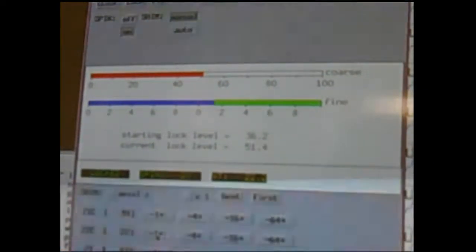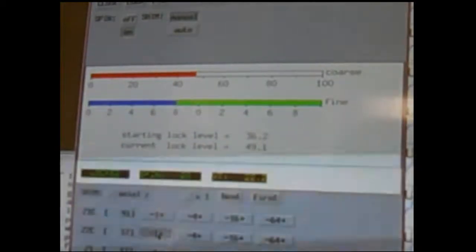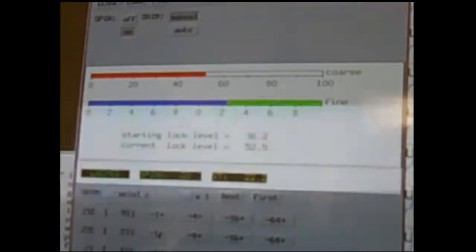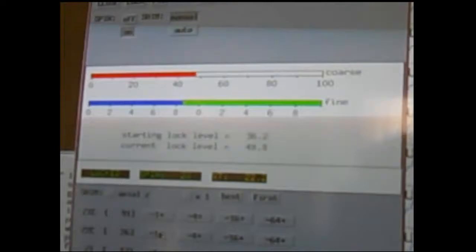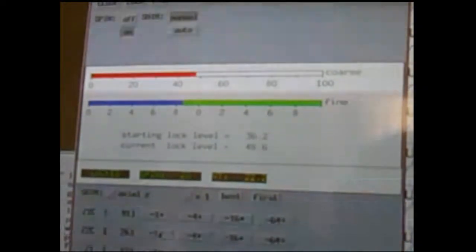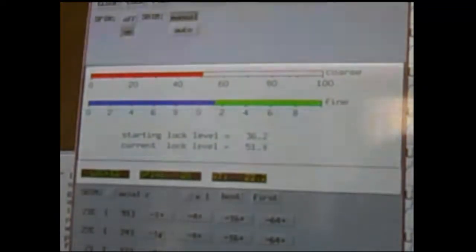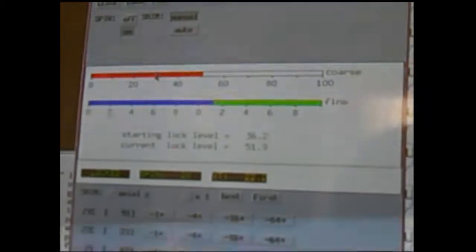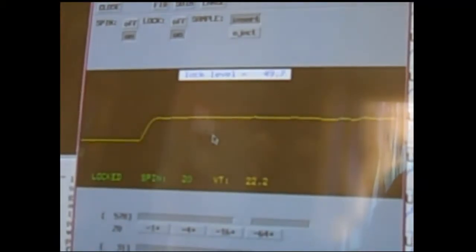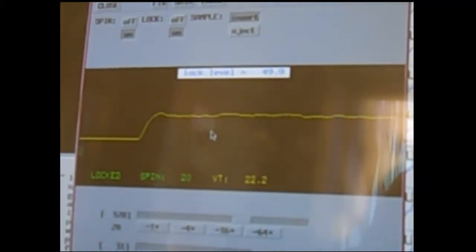Once I've optimized Z1C, then I'll optimize Z2C right here and do the same thing. Notice I've changed it and it's gone down, changed it and it's gone up a little bit. But if I go too far past it to the right, then I need to compensate, go back to the left so that I get the maximum number possible. Once you've optimized the Z1C and Z2C, you can go back out to the lock menu and ensure that your lock level is right around 50, which ours is.